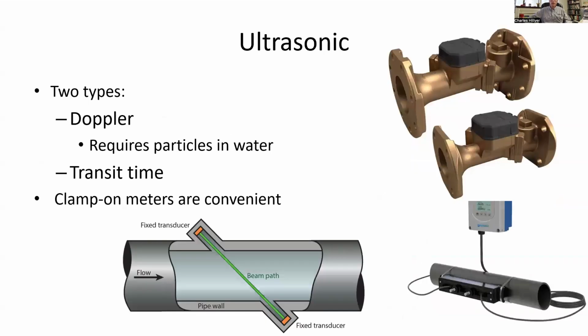Now, another type of device that's been around for a long time is the ultrasonic. There's two types of ultrasonic, one called the Doppler and the other called the transit time. The Doppler is special because it requires particles in the water. Those could be bubbles or bits of sand or anything. And so because of that requirement, Doppler doesn't get used too often in irrigation settings because we're dealing with clear water. The more common one is the transit time, and those are the figures you see over on the left. There's some examples of transit time.